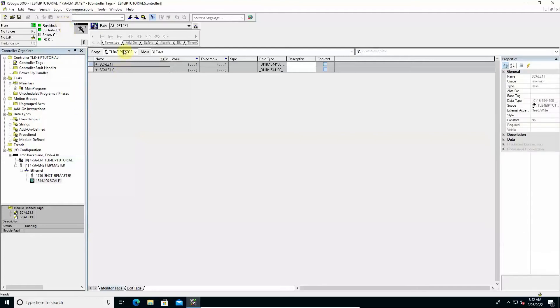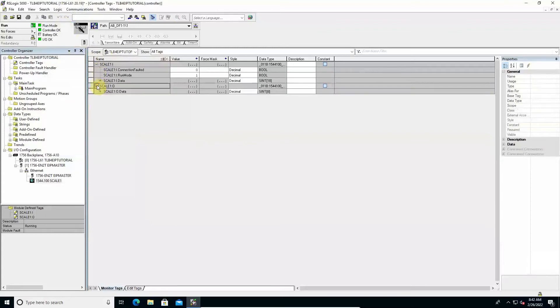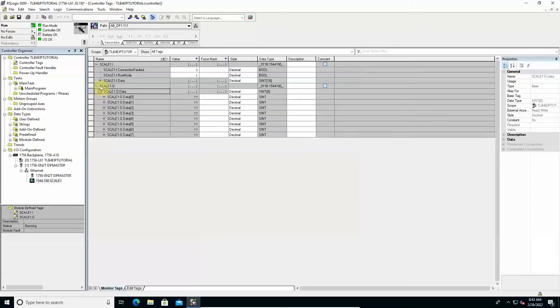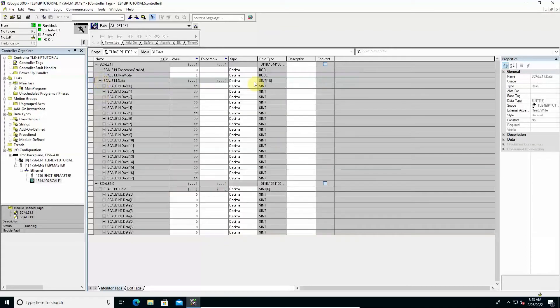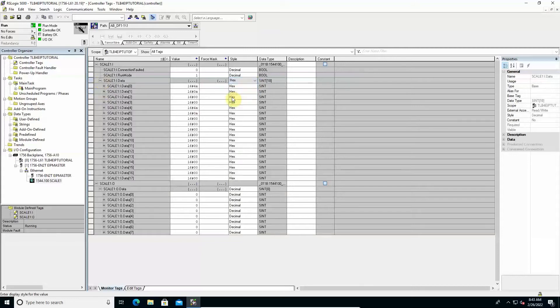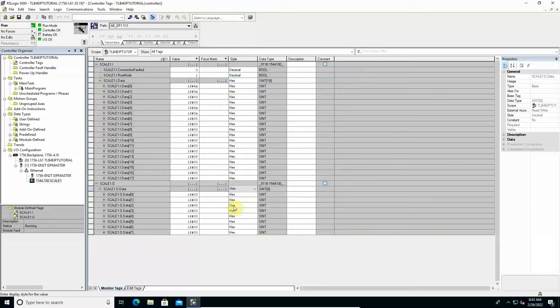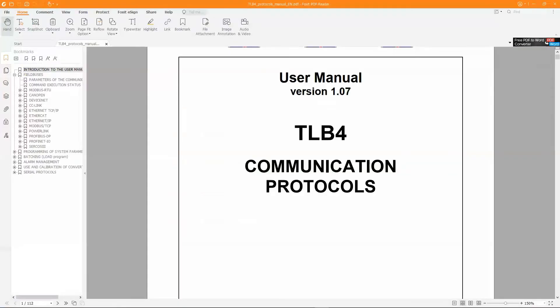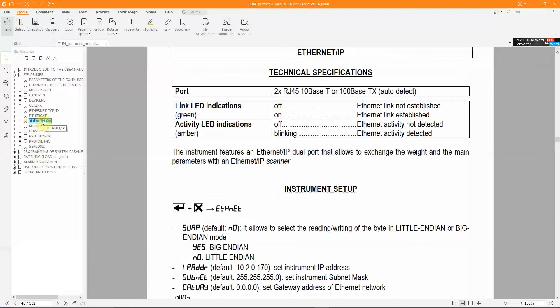The window that opens shows the data exchanged on the network, sorted using the communication structure contained in the TLB4 EDS file. Select the X format for both the input and output data sections to view the data in hexadecimal format. Using the TLB4 protocol manual, it is possible to properly manage this data.